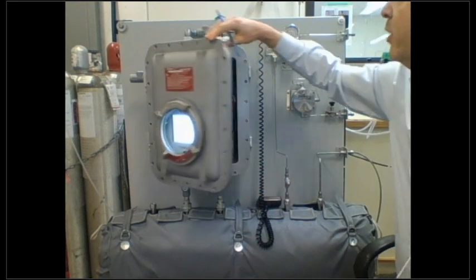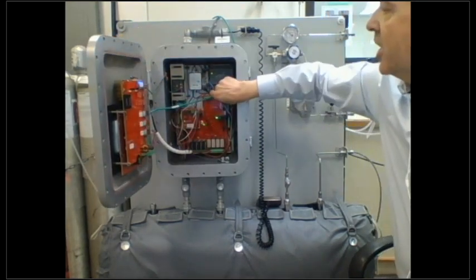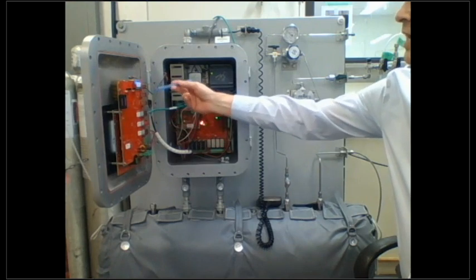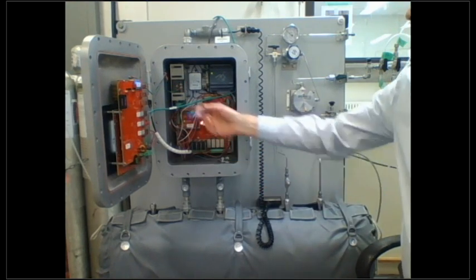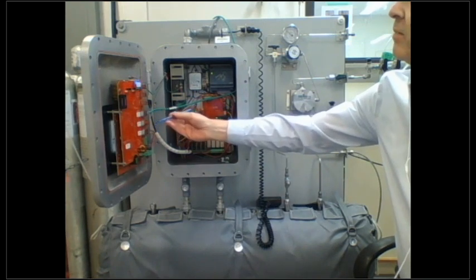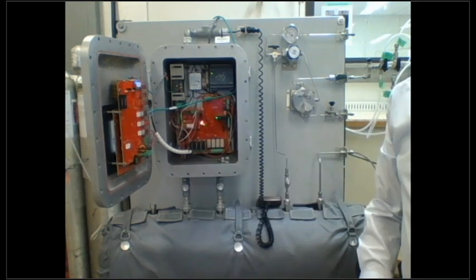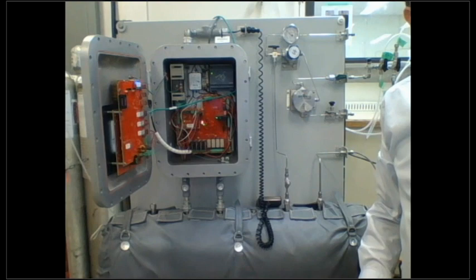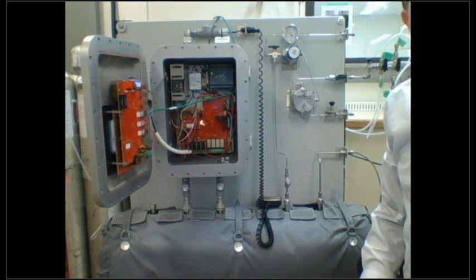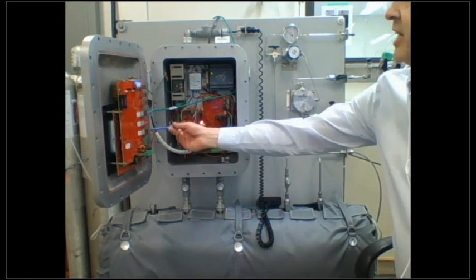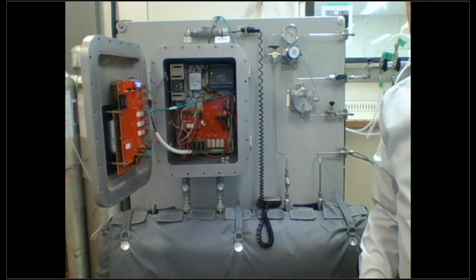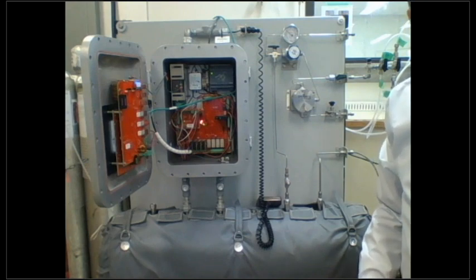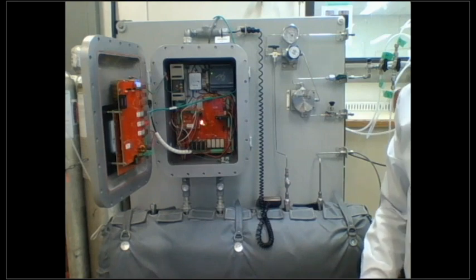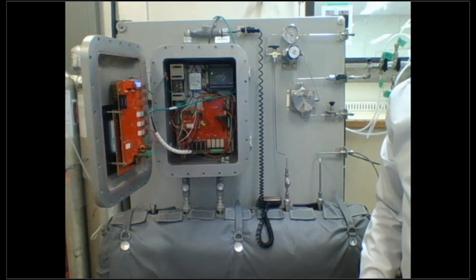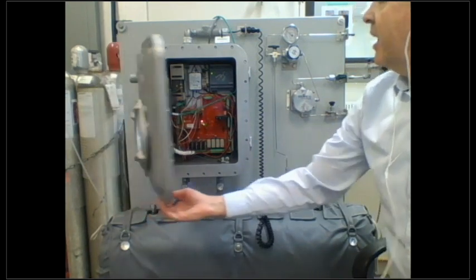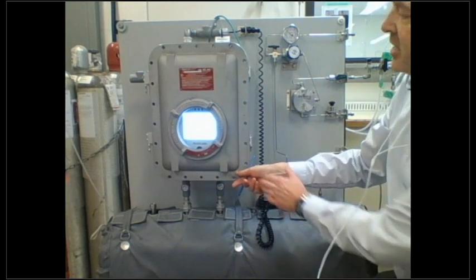On the door is a controller. This controller basically does all the computations necessary to generate the concentrations of gases that we're looking at. Also located there are some Ethernet ports as well as some USB ports. There are 3 Ethernet ports here. 2 of them are dedicated to network access, so you can plug into 2 different networks. The 3rd one is dedicated to a local Ethernet connection so that you can plug an Ethernet cable directly into a laptop. The analyzer has a dummy IP address that you can type in and communicate with it that way.